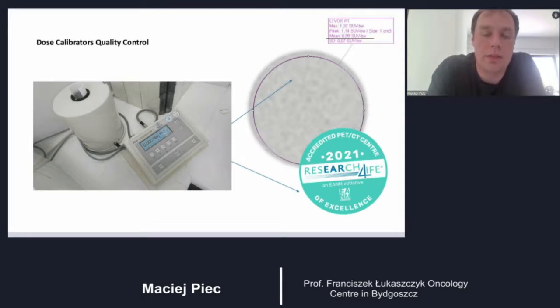But I have added the measurement on a phantom made with the use of a PET scanner. So our PET scanner needs to be calibrated with those calibrators. There is a kind of cross calibration where we calibrate the dose calibrator for a particular activity and concentration and SUV unit, so that SUV units are measured correctly. I have added this logo of our accreditation.